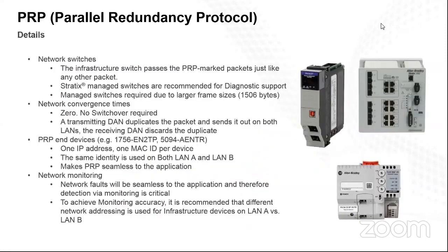Okay, and some more details. So how do we build a PRP network? First of all, we have to understand PRP packets are just like any other packet, but the DANs in the PRP network, the dually attached nodes, have the ability to send these PRP packets, and that differentiates.